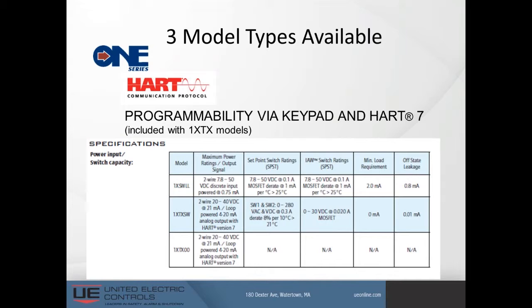All of these things can now be done from a HART handheld or a desktop calibrator, including the fact that if you want to set up DDs into this 1 series with the enabled HART, it can also be done. So if you want to put in a serial number, or you want to name this device, you can do it, and the DDs will then report back its address, so to speak. So that's the 1X TX SW.